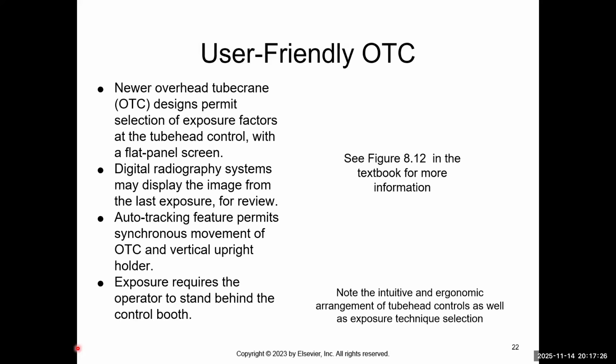And it also holds your last image for you. So on some of these, you can see the last image and easily start your manipulations. Like if you say, okay, I cut off the distal part, so I need to move my patient up a little bit so I can get the distal part. And then it allows auto tracking. I don't like auto tracking, and I don't think it's a feature that new students learning should use.